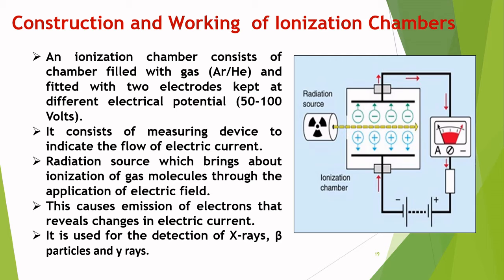Construction and working of ionization chamber. An ionization chamber consists of a chamber filled with a gas such as argon or helium and is fitted with two electrodes kept at different electrical potentials, 50 to 100 volts. It has a measuring device to indicate the flow of electric current. It has a radiation source which brings about the ionization of gaseous molecules via application of an electrical field. This causes the emission of electrons that is revealed by changes in the electrical current. Ionization chambers are used for the detection of X-rays, beta particles, and gamma rays.